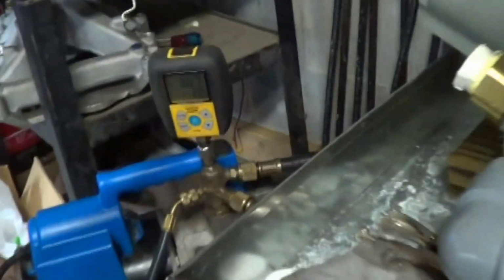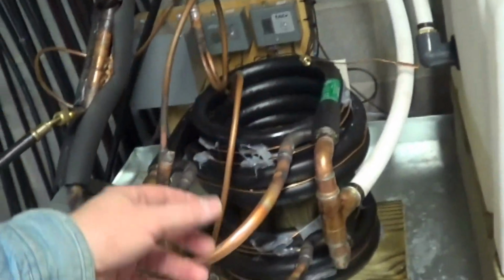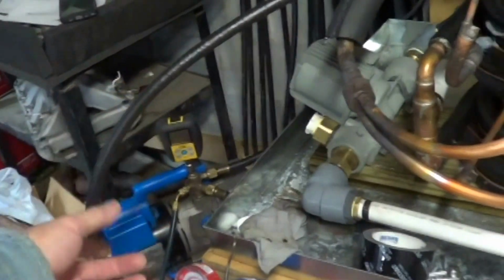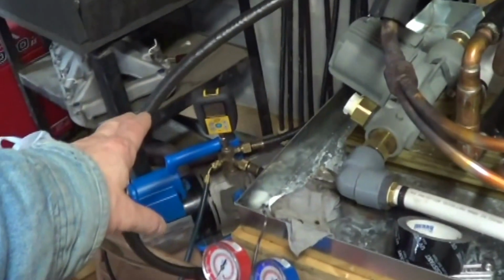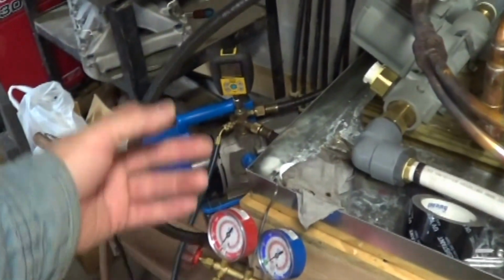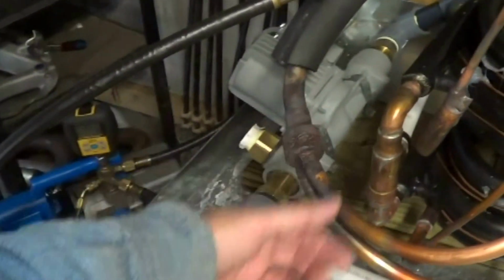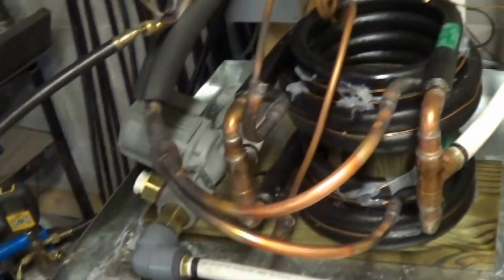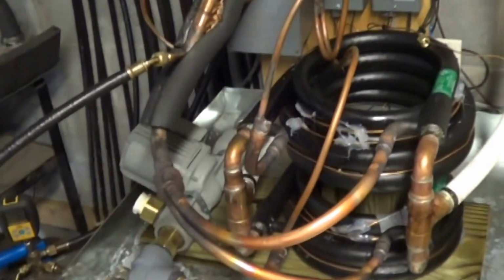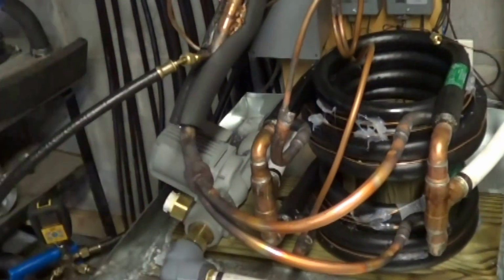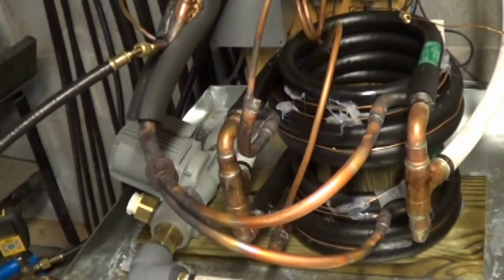Now notice on the evacuation it is not going as low. That's because there's oil in there, and the oil is boiling, so you don't have to worry if you're not going super low on the vacuum. It would eventually go if you boiled all your oil out, but there's no need to do that. And I'm still going to do a triple on this circuit, which is isolated. I have it isolated up there at the valves, so I don't have to pull down the rest of the system.